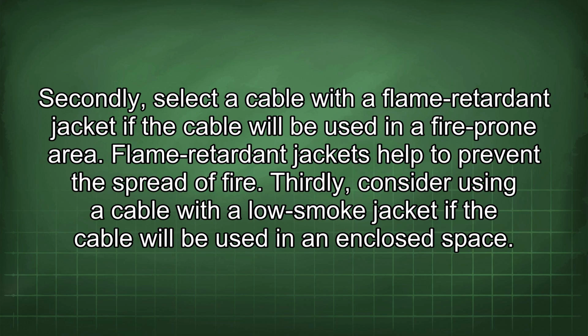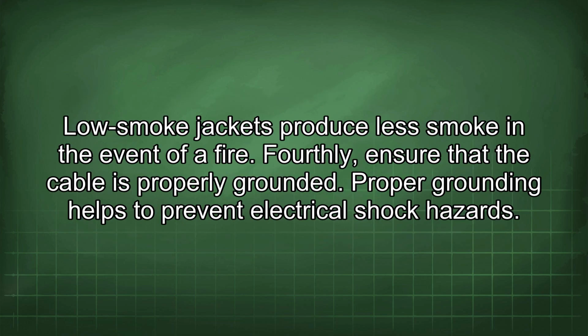Thirdly, consider using a cable with a low-smoke jacket if the cable will be used in an enclosed space. Low smoke jackets produce less smoke in the event of a fire. Fourthly, ensure that the cable is properly grounded. Proper grounding helps to prevent electrical shock hazards.